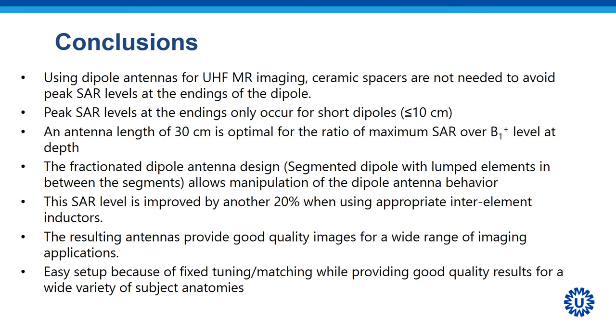In conclusion, using dipole antennas for ultra-high field MR imaging, ceramic spacers are not needed to avoid peak SAR levels at the endings of the dipole. Peak SAR levels at the endings only occur for short dipoles. An antenna length of 30 cm is optimal for the ratio of maximum SAR over B1 plus level at depth. The fractionated dipole antenna design allows manipulation of the dipole antenna behavior.